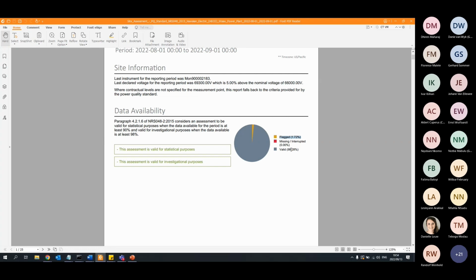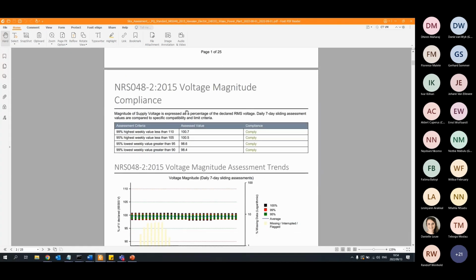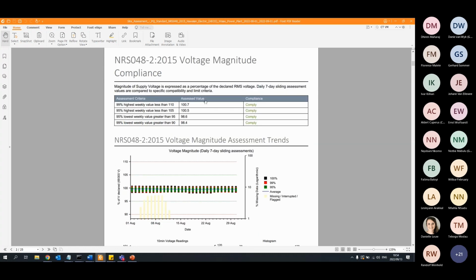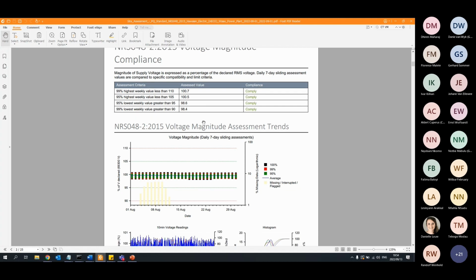So 98.28% of the data in this month was captured and recorded and is used then for the assessment that I will show you next. So the first thing is the voltage magnitude compliance or voltage regulation. Here's the example of a good voltage regulation where we can see that the limits, or the voltage regulation, is well within the upper and lower limits. You can see the 95th percentile upper and lower limit, and then the 99th percentile upper and lower limit. And you can see that the regulation is all very stable and close to 100% of declared.